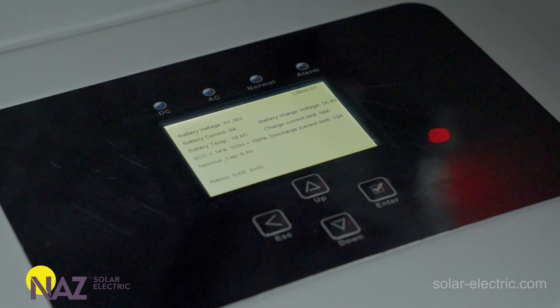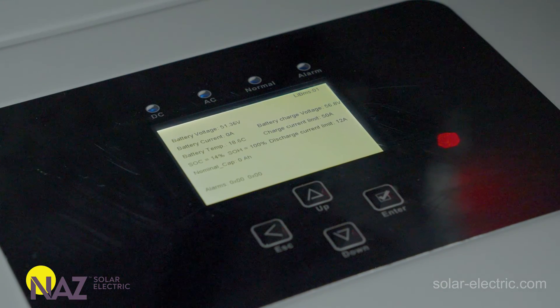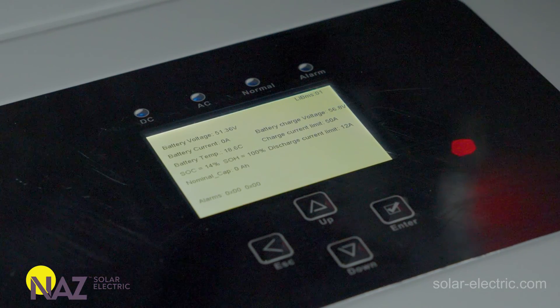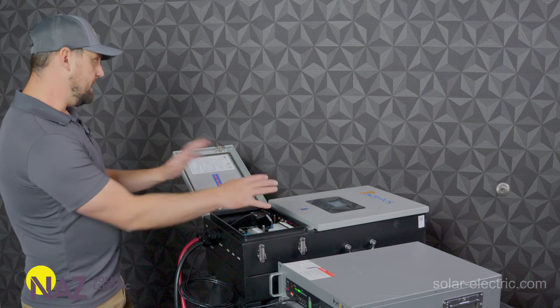We can look right now — the battery is providing battery voltage to the inverter. Internal battery voltage is providing SoC to the inverter. It's providing internal temperature to the inverter, and it's also defining the charging limits, current limits, and the discharging current limits.